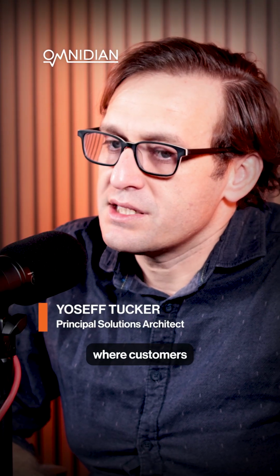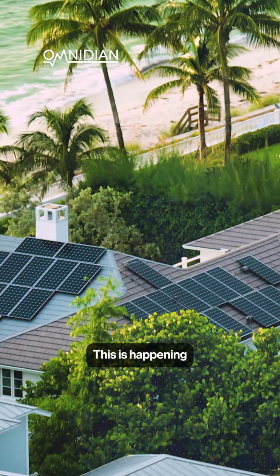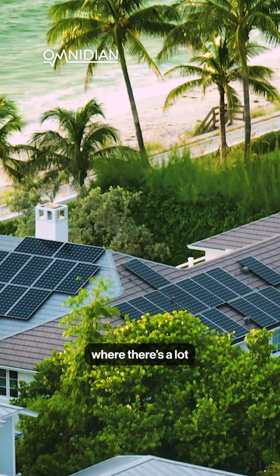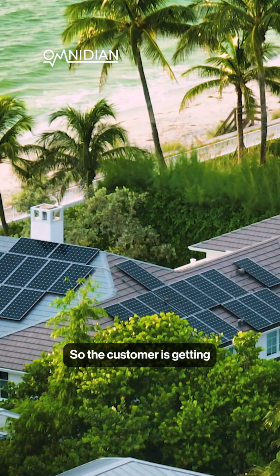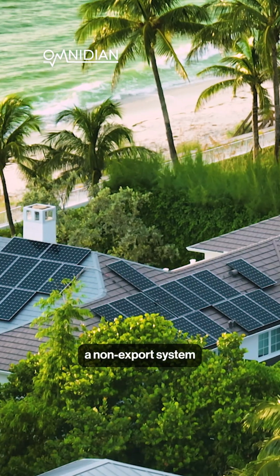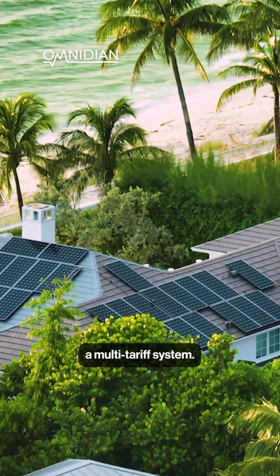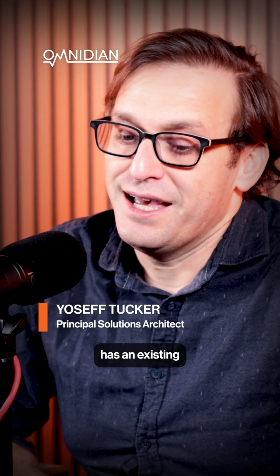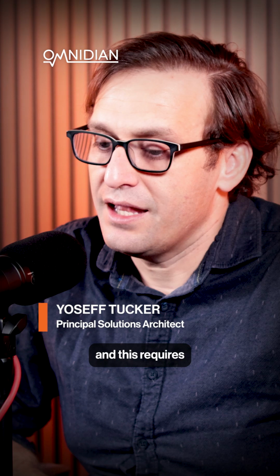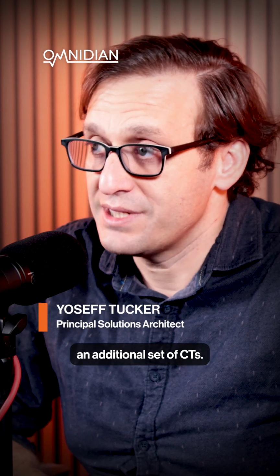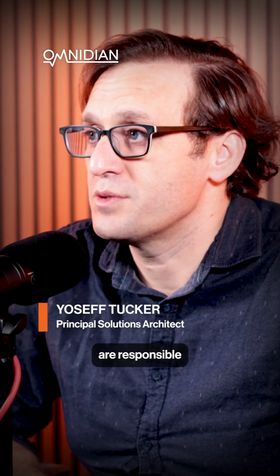The other thing we're seeing that's very related to this is certain configurations where customers are getting a second system. This is happening a lot in California, where there's a lot of market penetration. The customer's getting a second system, they call it a non-export system, or we'll call this a multi-tariff system. Now the customer has an existing solar power system and a new system, and this requires an additional set of CTs. So the installers are responsible for installing 4 CTs and getting every CT in the right location to be able to monitor the power.